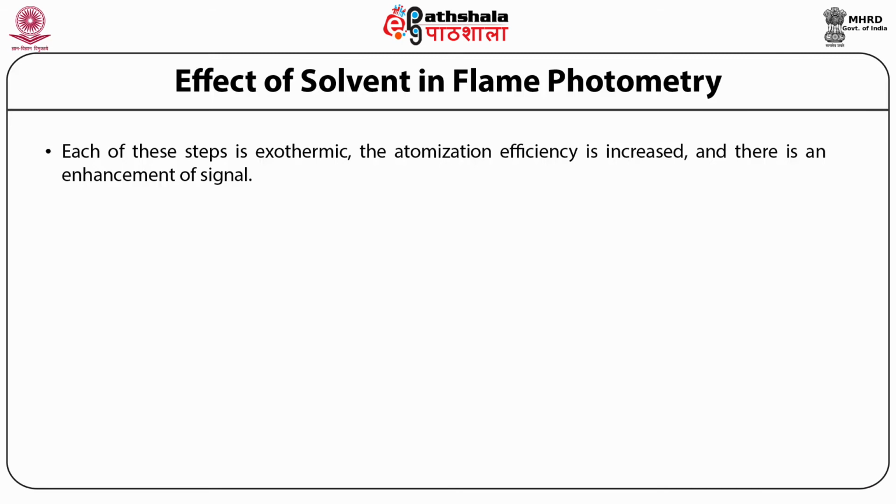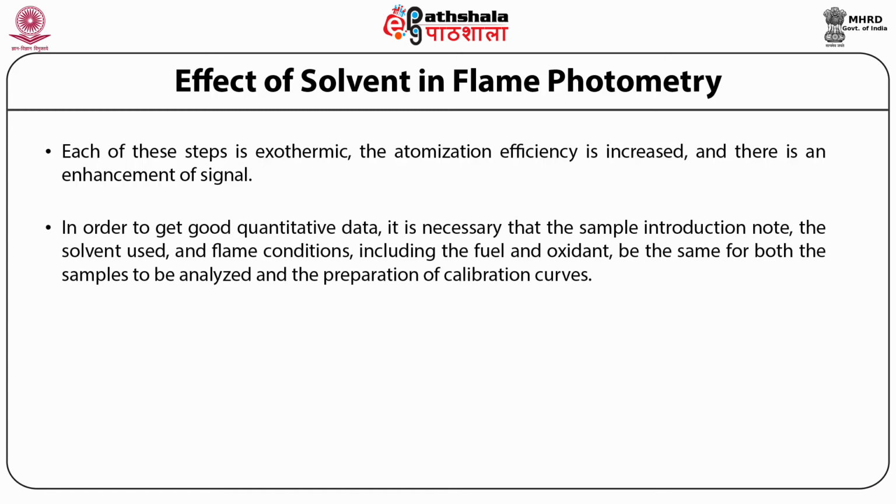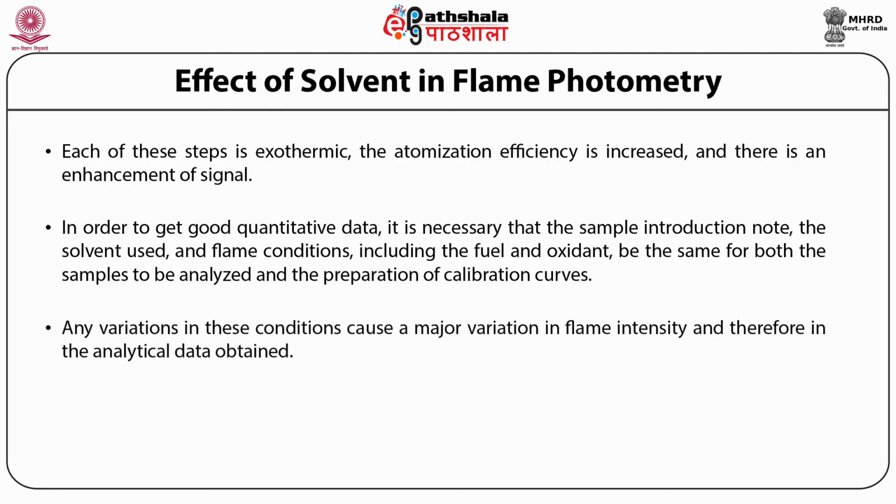It can be seen from these comments that in order to get good quantitative data, it is necessary that the sample preparation, the solvent used, and the flame conditions, including the fuel and oxidant, be the same for both the sample to be analyzed and the preparation of the calibration curves. Any variations in these conditions cause a major variation in flame intensity and therefore in the analytical data obtained.